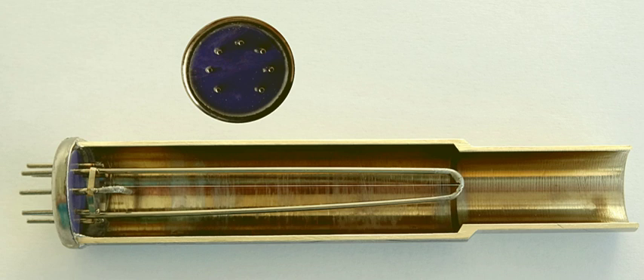The electrical resistance of a wire varies with its temperature, so the resistance indicates the temperature of the wire. In many systems, the wire is maintained at a constant resistance R by controlling the voltage through the wire. The resistance can be set using a bridge circuit. The voltage required to achieve this balance is therefore a measure of the vacuum.